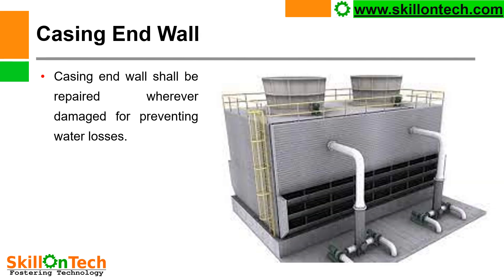Here you can see the end wall casing. This shall be intact with the cooling tower, but it can become damaged over a period of time. If the end casing wall is damaged, water can splash out into the atmosphere and water losses will increase. So the casing end wall shall be repaired wherever damaged to prevent water losses.